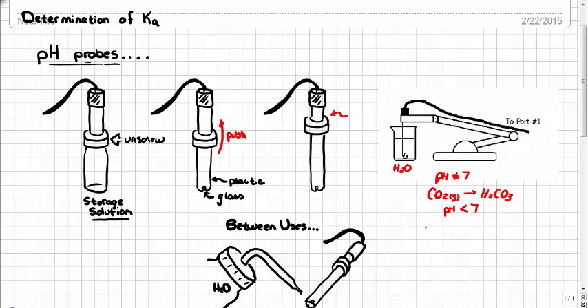Now, to just jump ahead a little bit, if you're finished at the end of the day, what you need to do is you need to return the pH probe back to the storage solution. That's going to mean having to take the lid, which is currently in this position, and to carefully push it down to approximately the same place it was when you first began. This is very important because in its extended position, the pH probe, when put into the storage solution, can actually crash into the bottom of the storage solution vial. Doing this will likely break the end off the pH probe. These are not repairable, and so the pH probe would be ruined.